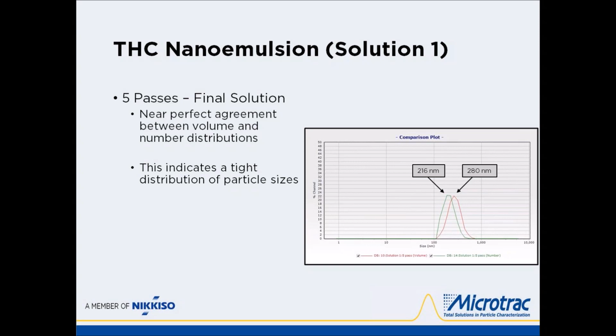Again, the third pass is not too much different from the second pass. We're starting to trend toward uniformity when it comes to particle size distribution. And for our first solution at 5 passes, you can see we've got near perfect agreement between the volume and the number distribution, with the number distribution being at 216 nanometers, with the volume distribution having a peak at 280.